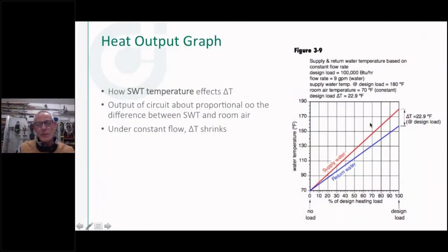All right, so here's the heat output graph. Let's put some numbers on this. I'm not going to do a lot of math and formulas. I like doing the visuals, but it's important to know the math behind all these pictures. So let's design a system. Let's say we've got a 100,000 BTU load, and we're going to flow through this loop. Let's call it a fin tube loop. It could be a cast iron radiator; it doesn't matter what the heat emitter is. We're going to supply that with 180 degrees, in a room with an air temperature of, say, 70 degrees. At my design condition, the delta T came out to 22.9 degrees.